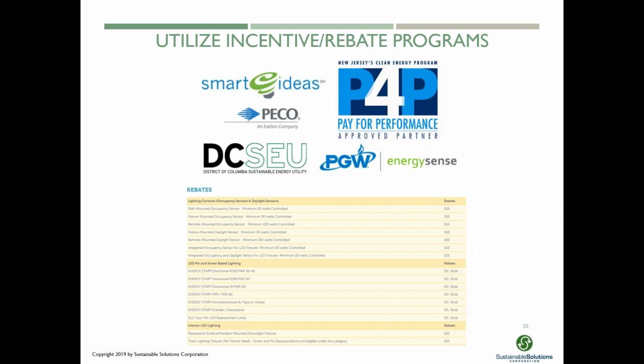So not only were they using like 150 watts per bulb, but they were also creating like this giant oven effect where you had almost 200 of these bulbs giving off a ton of heat. And basically, jacking up the cooling requirements for the space and just the lighting loads.